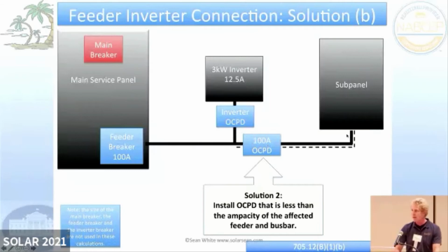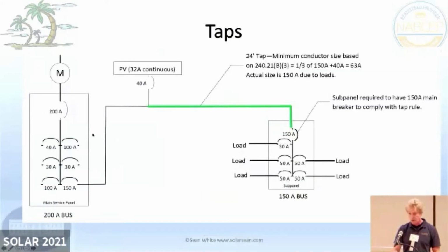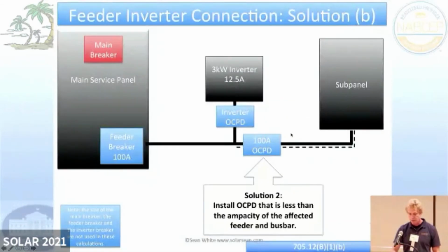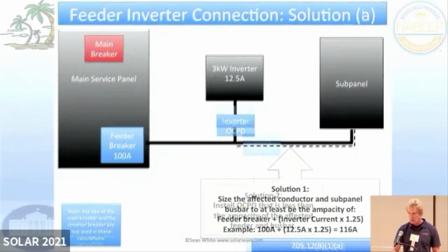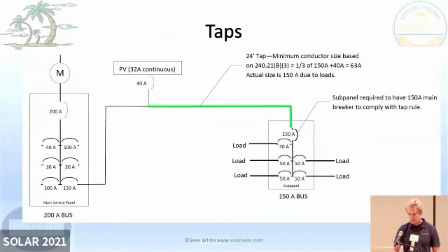But when you get down to this stuff, it gets really difficult. And then also under engineering supervision, you can do it all kinds of different ways. If you had a professional electrical engineer, you could do it a different way too. And that's actually there in the code. We have some different numbers, but same thing. So there's the feeder breaker, and then there's the inverter. And then if we're within 25 feet, so it says 24 feet, we can put it there in that position. This type of stuff here too that I was just showing you about tapping the feeder, I don't see a lot of people even doing this, but those are the rules out there.